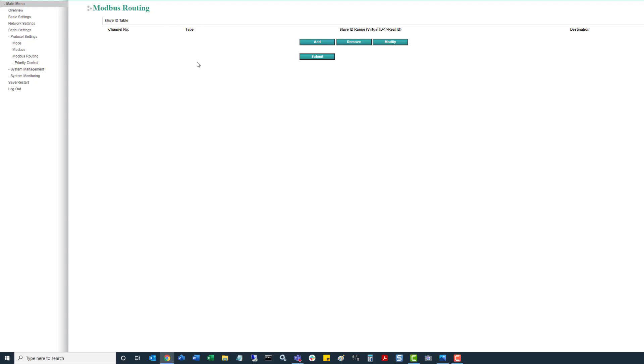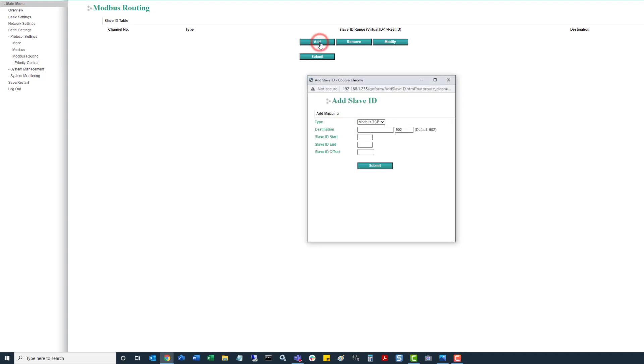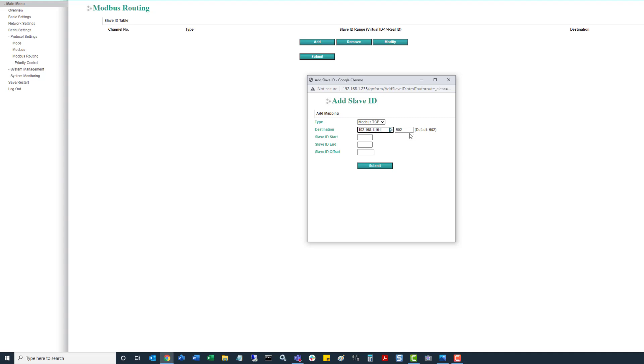So starting off initially what we want to do is click on this add, and it's going to open up this second window. For type, we want to select Modbus TCP. And then we're going to type in the IP address of that field controller. So in this example, if you're using an alternative port for Modbus TCP outside of 502, you can update that here.